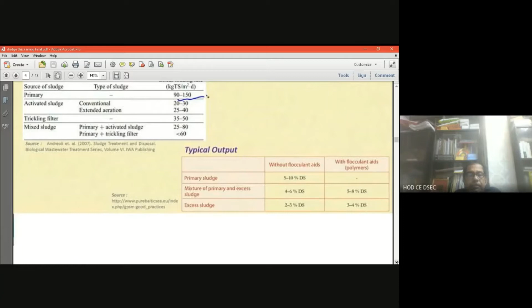Where the mixture of primary and excess sludge is there, the primary without flocculant aids is 4 to 6% DS, that is the dry solid, and with flocculant aids it will somehow increase to 5 to 8%. You must observe that for primary sludge, flocculant and polymers will have no effect, because we use flocculant and polymer for the secondary and tertiary process. That is the primary and excess sludge.